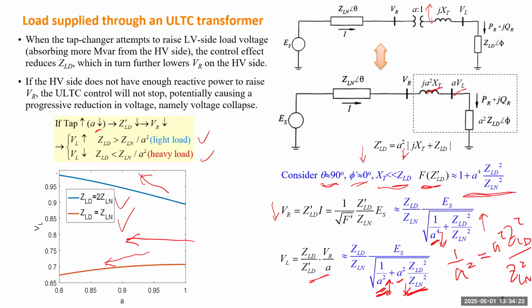In order to prevent the system from moving onto the wrong curve and to maintain it on the blue curve, we really need to have the entire system model. Then we will know when we need to either stop this control or reverse direction. That's why typically, when the operators or engineers notice there could be potential voltage collapse, the first thing they need to do, among a number of items, is disable the tap changing transformer before they make sure they have enough margin. When the margin to the stability limit is enough, it's okay to let the tap changing transformer work. But if the margin is small, they need to disable the tap changing.